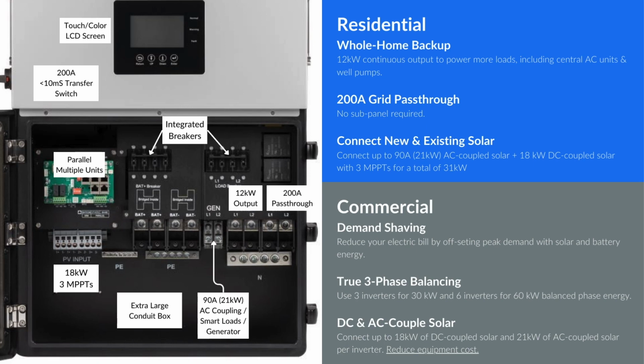There's integrated load and battery breakers, which help reduce balance of system costs. There's 3 MPPTs that allow up to 18 kW of DC coupled solar. There's an extra large conduit box, which makes installation of these large gauge wires very simple. There's a generator port for 90 amp AC coupling. You can also use this port for smart load. You can also connect an auto start generator. There's 12 kilowatts of continuous output, which is amongst the highest in the industry.